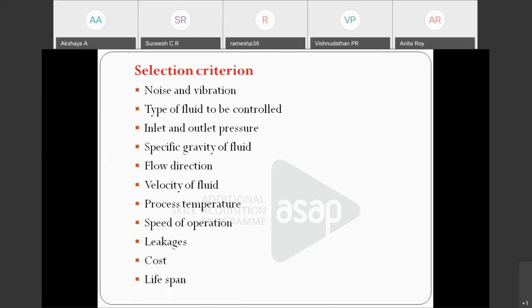Then another thing is the inlet and the outlet pressures. So that is also an important thing. Then the specific gravity of the fluid, the flow direction, the velocity of the fluid, and the temperature of operation, which is a very important factor in particular actuators. The leakage, cost, lifespan. These are the broad points to be taken care of while you are choosing a particular valve for a particular application. Next.